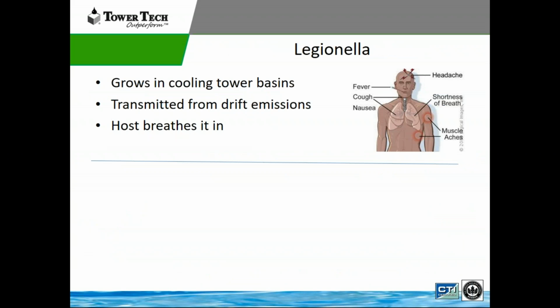So we're going to talk about Legionella from a cooling tower standpoint. It typically grows in a cooling tower basin with stagnant water and transmits through the drift emissions. As I mentioned earlier, when you walk around a traditional tower, when you go up on the roof or on the side of a building, you'll notice the droplets of water when that machine is operating in the summertime. At that point, sometimes the drift goes into an outside air duct, or it's inhaled somehow at the job site, and that's a lot of the cases where we see Legionella.